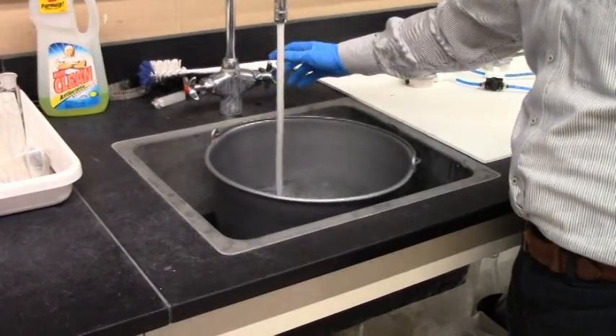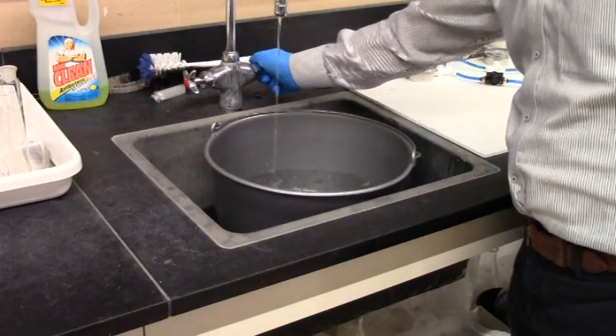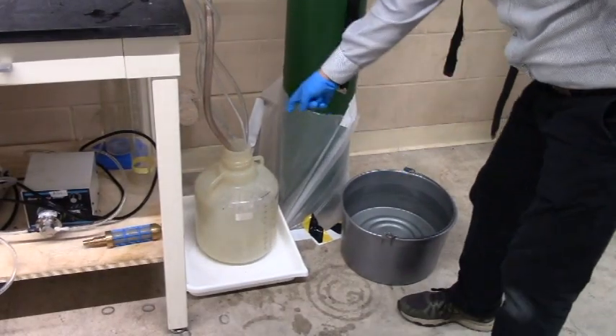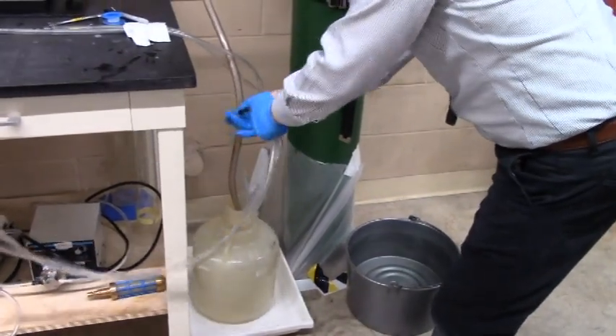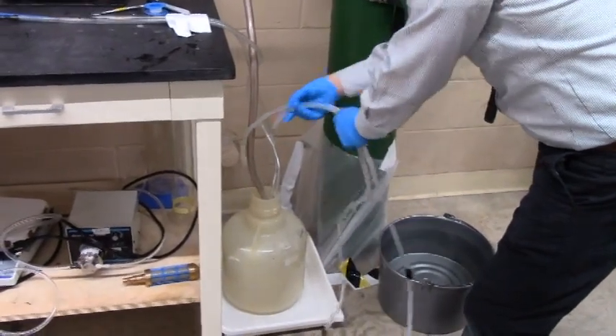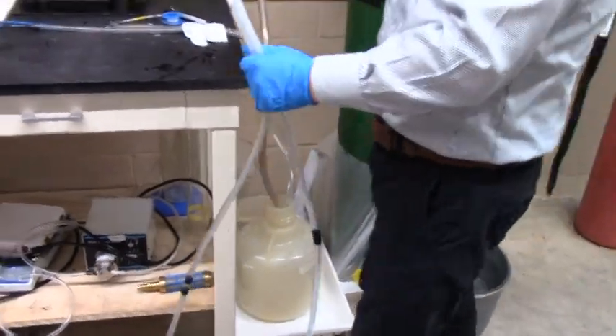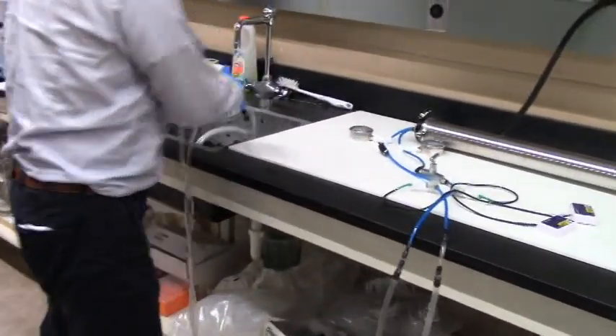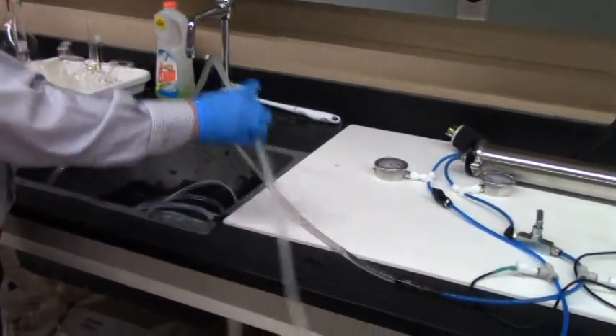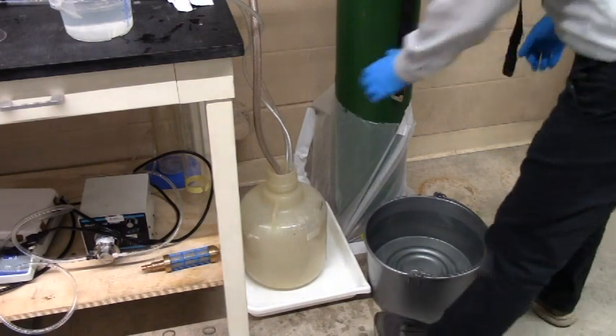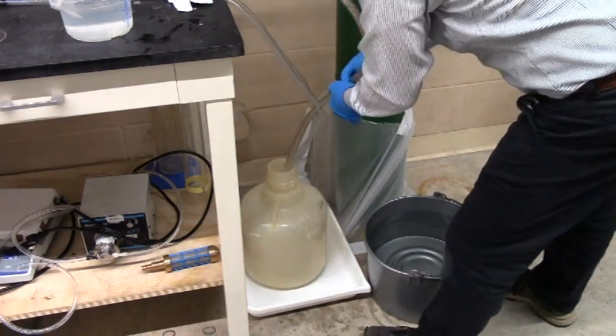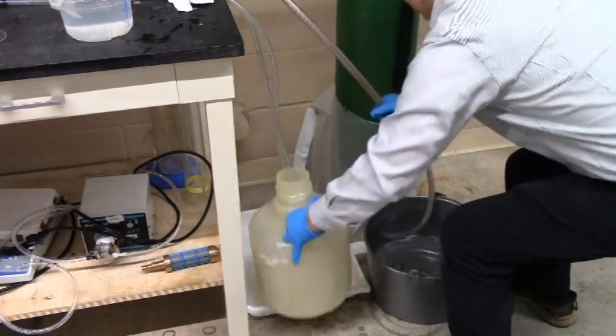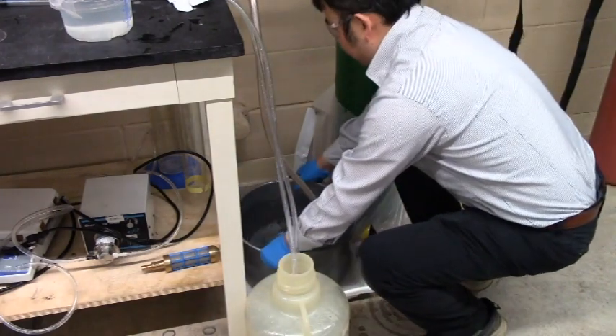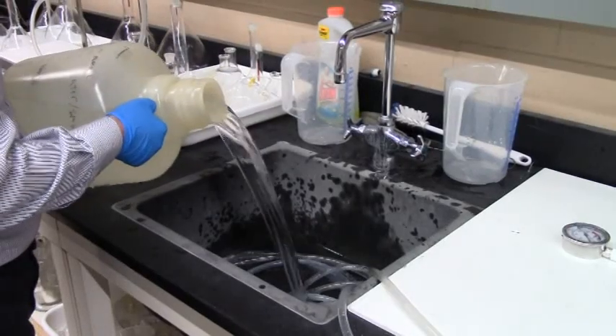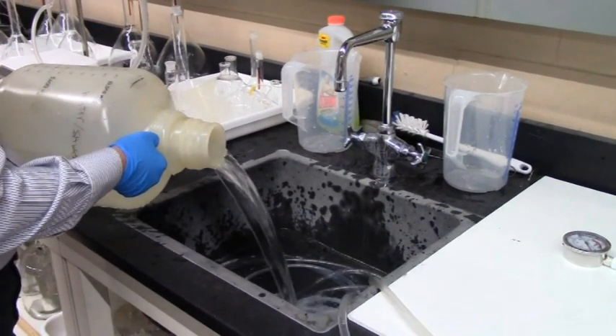In the sink, fill the bucket with tap water to about 3/4 of the height again. Move the bucket next to the carboy on the floor. Move the two long tubes for reject and filtrate lines from the carboy to the sink. Move the pump suction tube from the carboy to the bucket. Then move the bucket onto the white tray, which is a secondary containment. Empty the carboy into the sink. Move back the carboy and insert the bypass tubes.